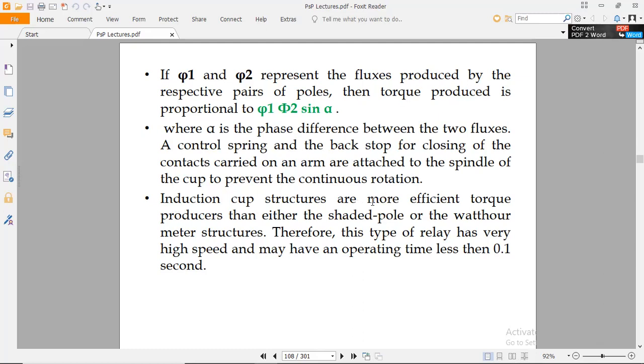Induction cup structures are more efficient torque producers than either the shaded pole or the watt-hour meter structures. Therefore, this type of relay has very high speed and may have an operating time of less than 0.1 second. On this basis, we mostly prefer the cup-based protection relay.